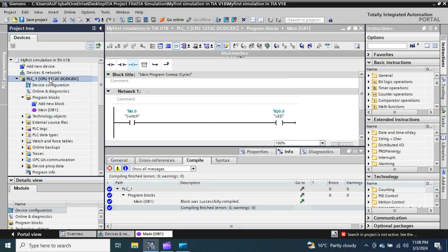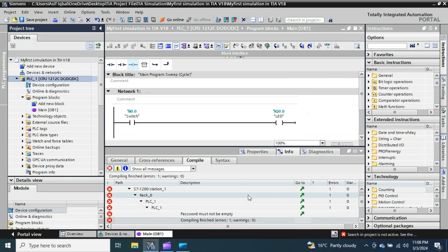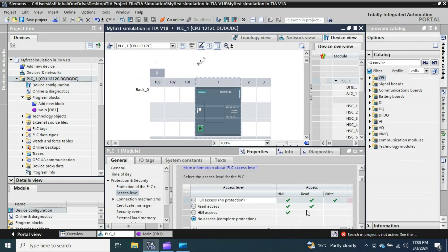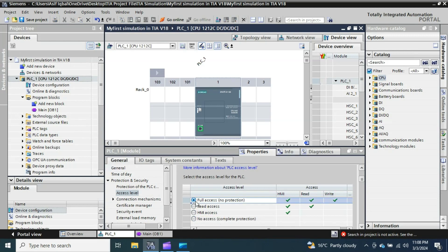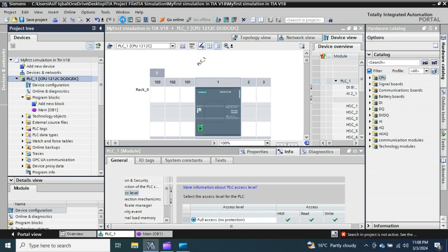Now I will select the PLC and compile all the PLC blocks to check for any errors. It is showing me an error: the password must not be empty. Even though I told TIA Portal I don't want a password, it is still flagging this. I double-click the error, go to the protection settings, and change it from 'No access — complete protection' to 'Full access with no protection'. Now I select the PLC again and compile once more.